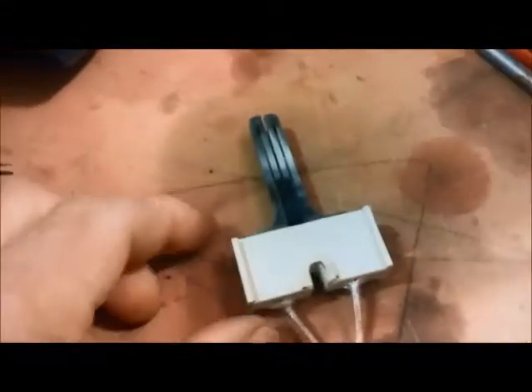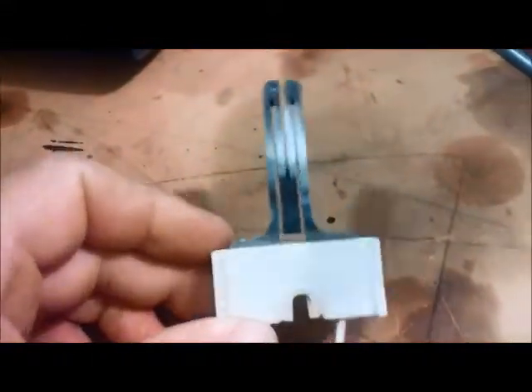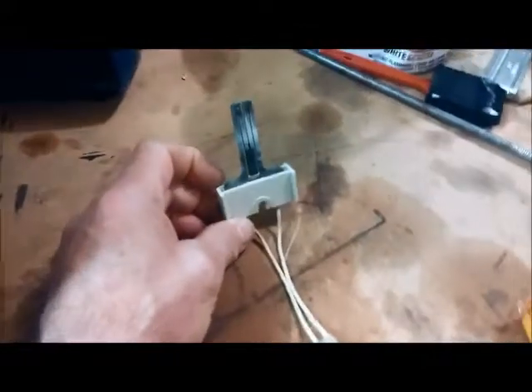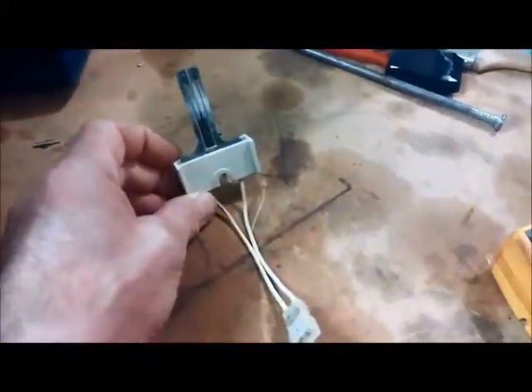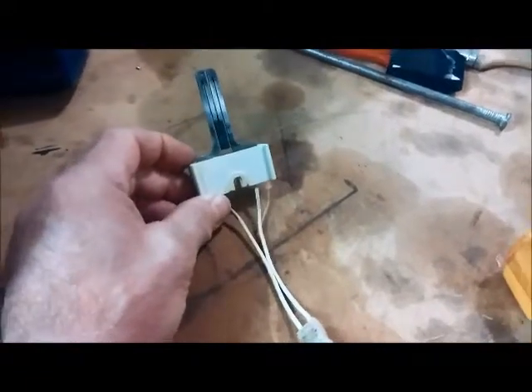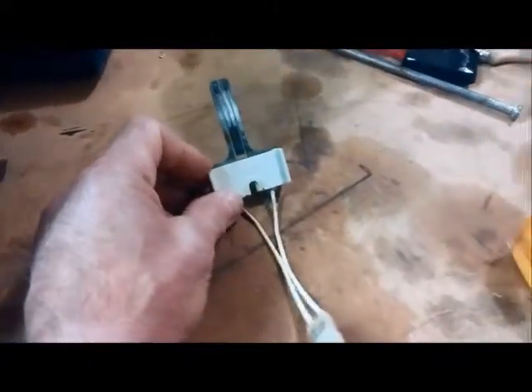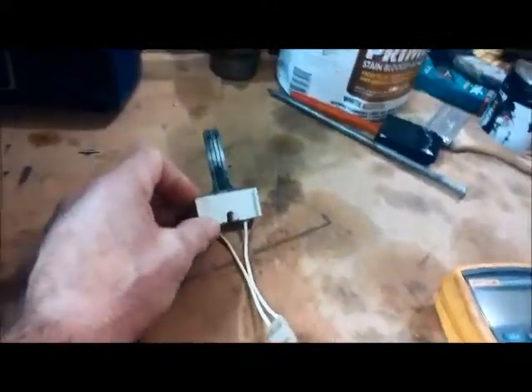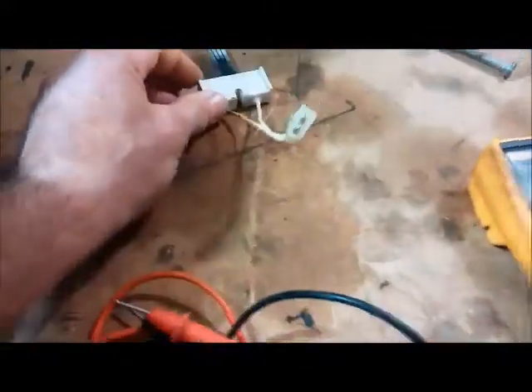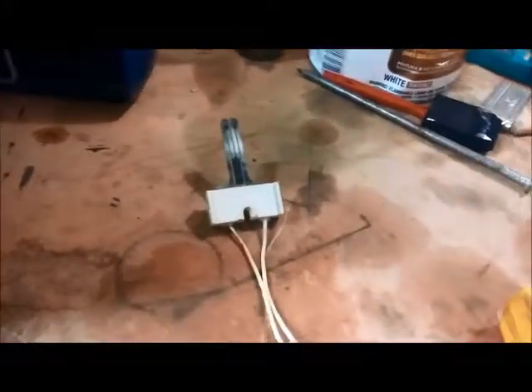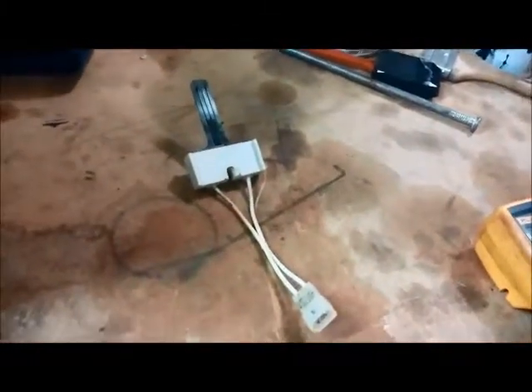Your igniter, this one here, is measuring at 100 ohms. You know, I bet this has been in that furnace. I just took this out the other day. It was measuring 90 ohms because it was hot. I just measured it on the bench here, and she was measuring at 100 ohms. So this didn't have much life in it. A new one's going to be right around 60 ohms. Once they hit 100, probably just change them. I like to let them go, but if you're on call where they're 100 ohms, you should talk the customer into changing it. That one there would still work for how long? I don't know.